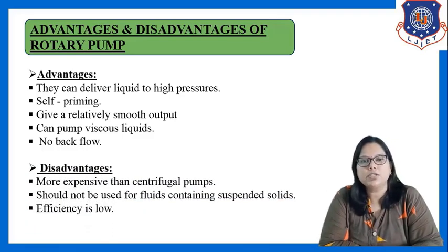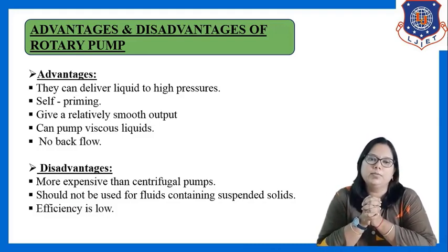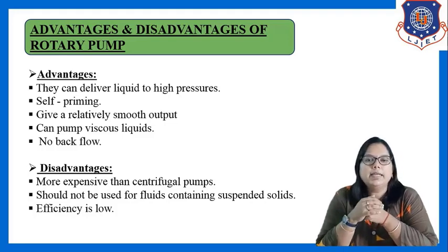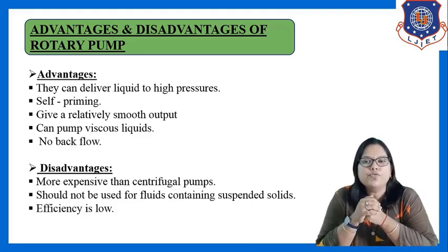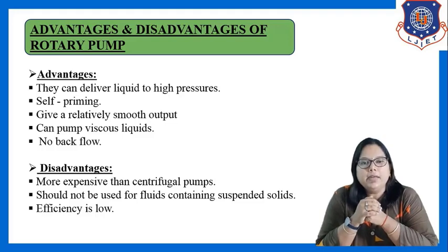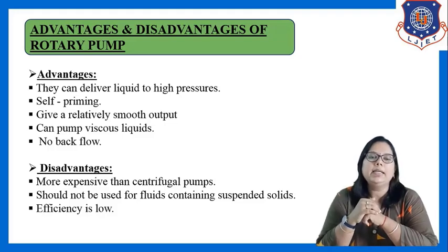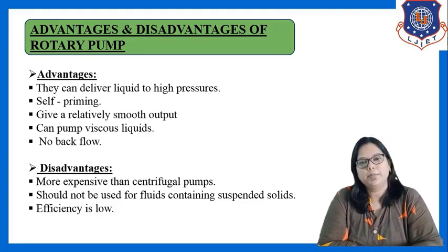Let us see disadvantages of the rotary pump. This rotary pump is more expensive than centrifugal. Another disadvantage is it should not be used for fluids containing suspended solids. If we have to transfer fluid containing suspended solids, then we cannot go for rotary pump. And the last disadvantage of the rotary pump is the efficiency of the rotary pump is very low. So these are the advantages and disadvantages of using rotary pump.